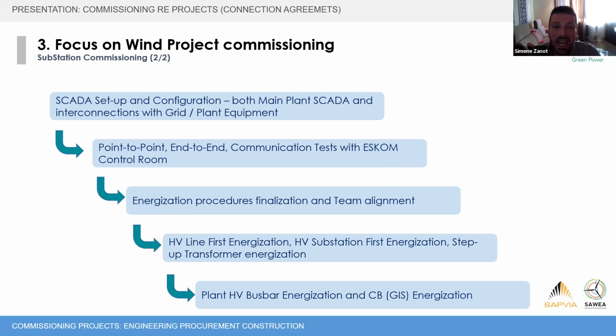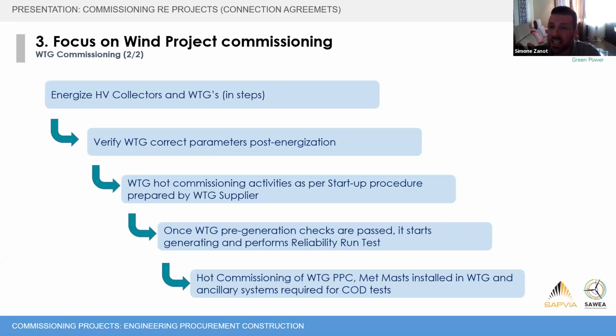After the substation is energized, we energize the HV collectors, which link the generating systems, the power conversion units, or the wind turbines to the substation. We energize the wind turbines or the power conversion units in case of PV.